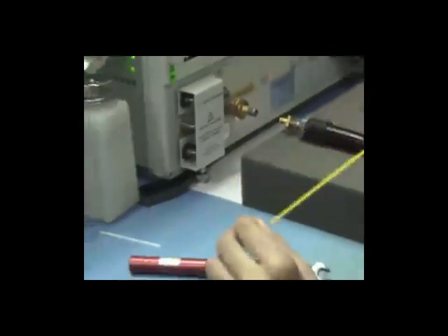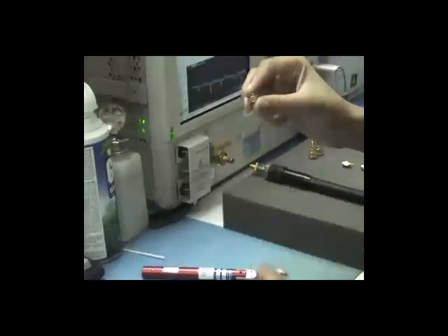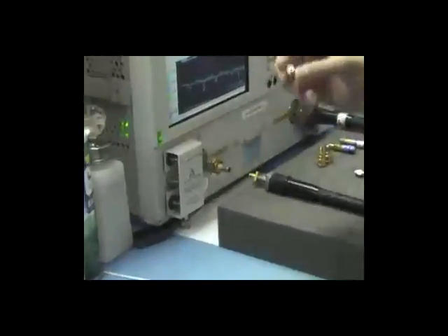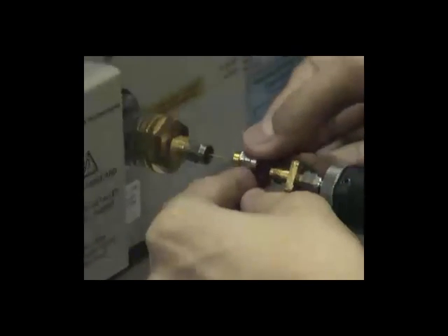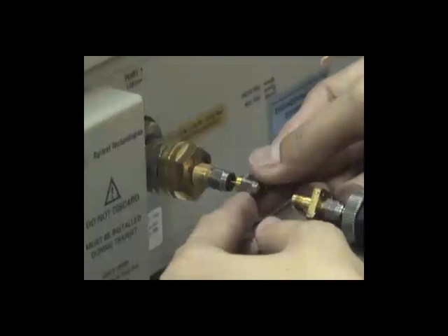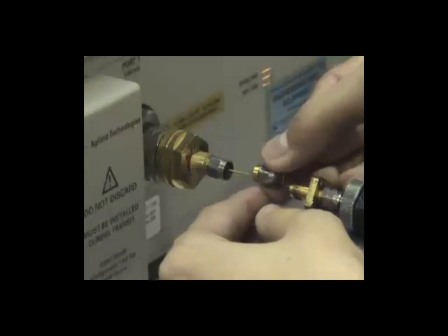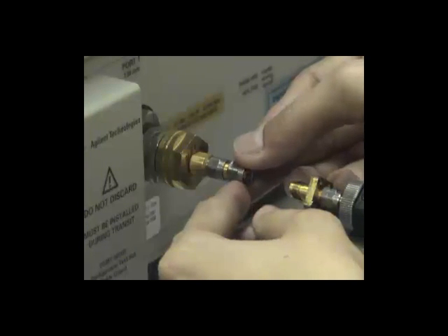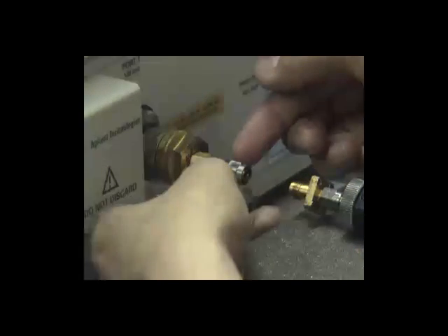Once you've put the contact on or even before you put the contact on, what you could do is make sure that the body is clean through the bore. Just spray some air and clean any dirt or anything that could be sitting inside this body here. You have to realize that it's only 1.85 millimeters in diameter this hole, so when we align it and get it over, make sure you're going in straight and you don't hit the contact while trying to find the hole, because by hitting it you are stressing the contact.